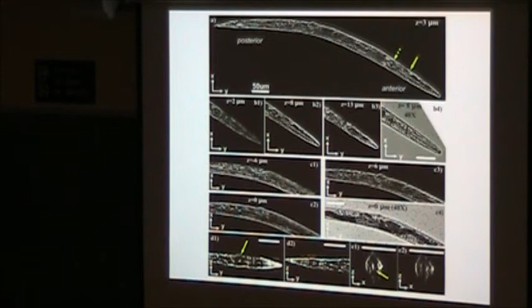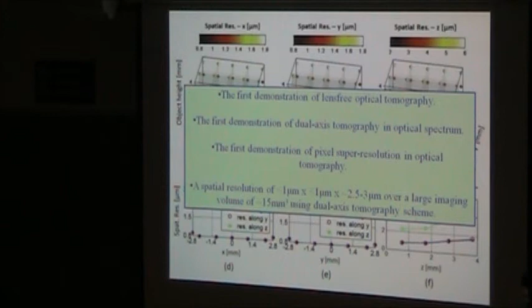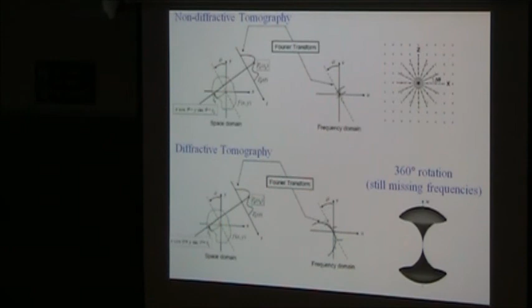If you want to make this larger, like 50 millimeter cube or 100 millimeter cube, what we'll be losing is mostly the axial resolution, but still you can look at larger depth of field with a reduced spatial resolution, mostly coming because of the signal-to-noise ratio limitations. None of these sensors are actually cooled sensors. They were room temperature, simple CMOS sensors. In that sense, there's a lot of room to improve, especially the CMOS end of our sensors.